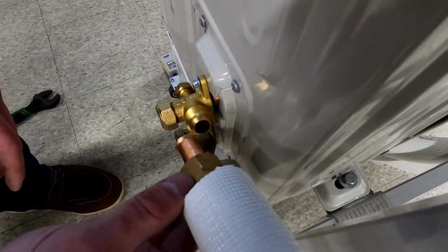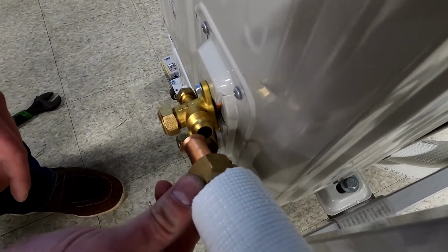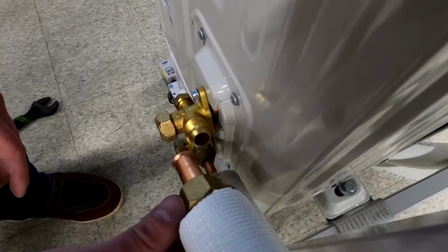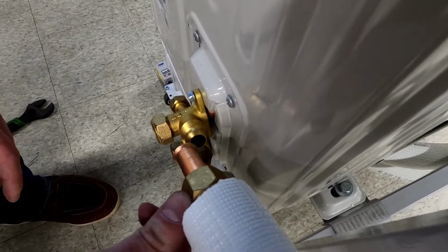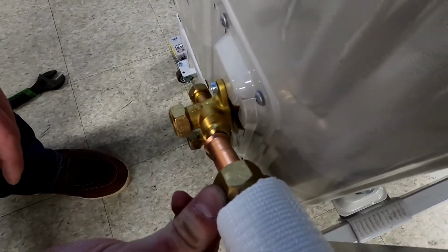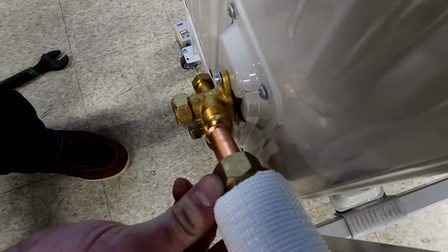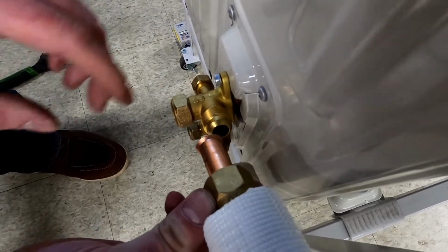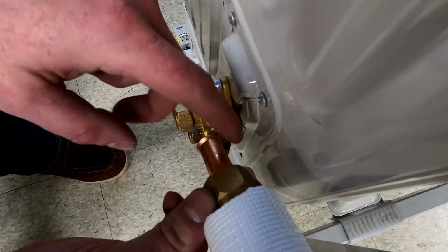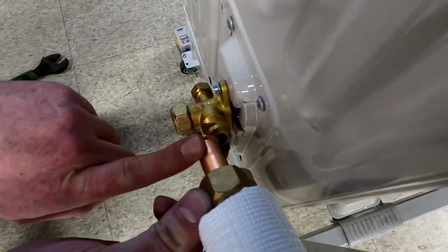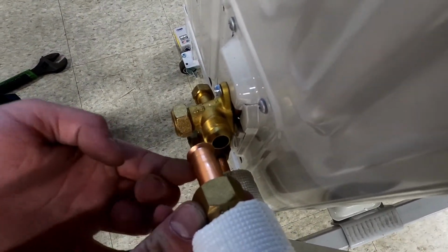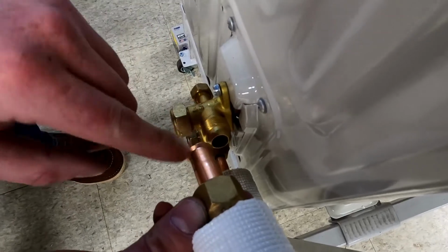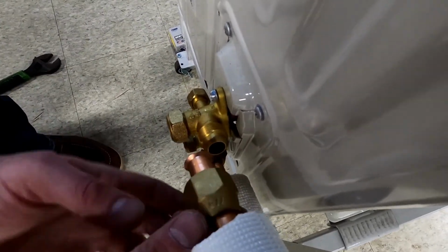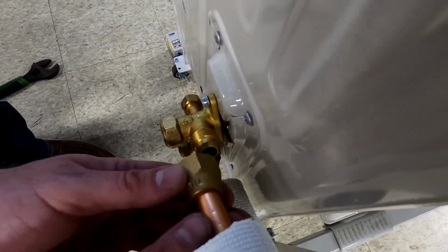All right, now we're ready to torque down our flares to the service valves. One thing that's extremely important is that you use a proper torque wrench when you're making these connections. When you're ready to make your connection, use a little bit of oil, preferably refrigerant oil, and put it around the cone of the flare. That'll prevent it from twisting the pipe as you get to your maximum torque.